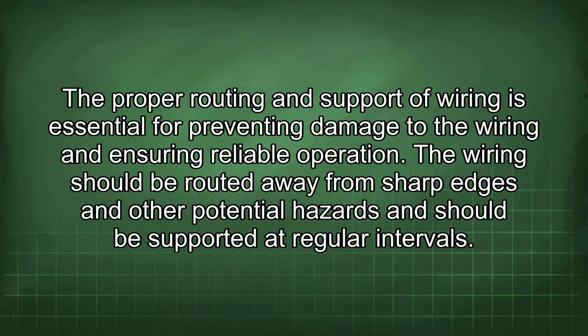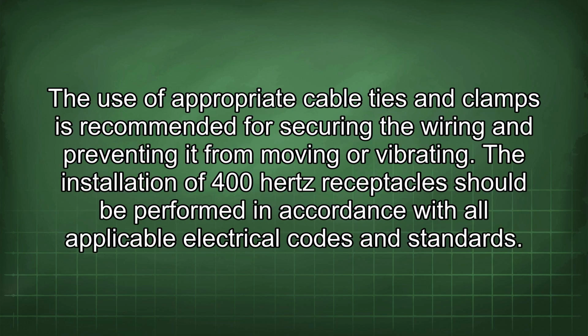The proper routing and support of wiring is essential for preventing damage to the wiring and ensuring reliable operation. The wiring should be routed away from sharp edges and other potential hazards and should be supported at regular intervals. The use of appropriate cable ties and clamps is recommended for securing the wiring and preventing it from moving or vibrating. The installation of 400 Hz receptacles should be performed in accordance with all applicable electrical codes and standards.